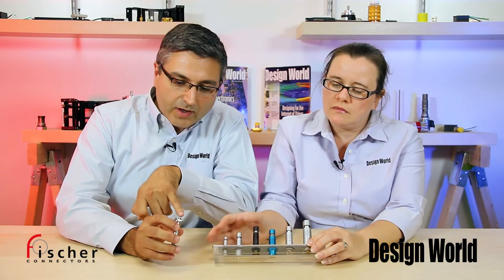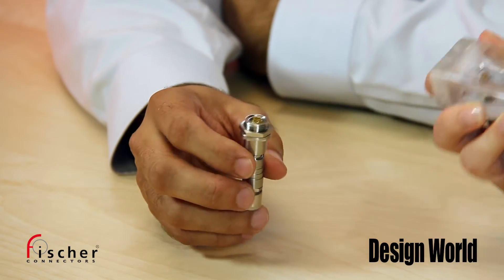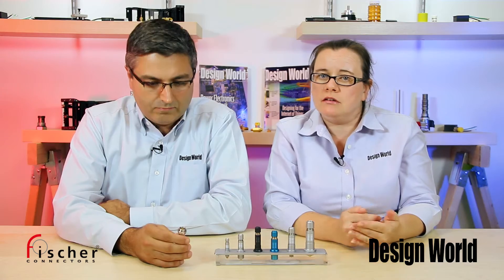Well, these contacts are kind of unique here too. I'm used to seeing a more flat type of contact. Yeah, that's what Fischer calls its half-moon keying, which prevents a user from damaging a connector if they try to put a plug into the wrong receptacle. It also prevents you from actually mating something that shouldn't be mated. Fischer has four standard keys that it uses and can also build custom keys for its customers as well.